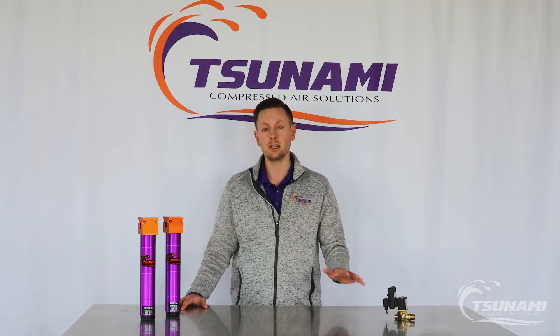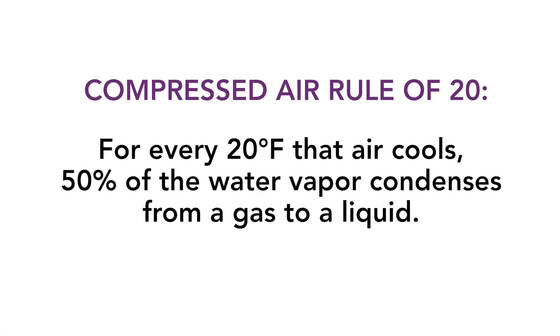Within any air system, there's a rule of 20. For every 20 degrees of that air cooling in your compressed air piping, 50% of that water vapor will condense from a gas to a liquid.